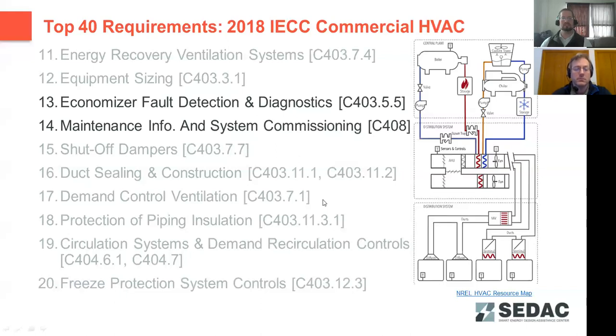Our next section is the 2018 IECC Commercial HVAC section. Again, in our full-length presentations, we cover 10 different items that we considered the top 10 issues for compliance or issues that we see when we go out and check buildings for assessments. What we wanted to cover today specifically were Economizer fault detection and diagnostics, since that's new to the 2018 IECC, and maintenance info and system commissioning, mainly focusing on commissioning because the 2018 updated their language for a lot of control systems, saying that instead of being just capable of certain controls, they now have to be configured and working when the building is turned over to the operator or to the owner.